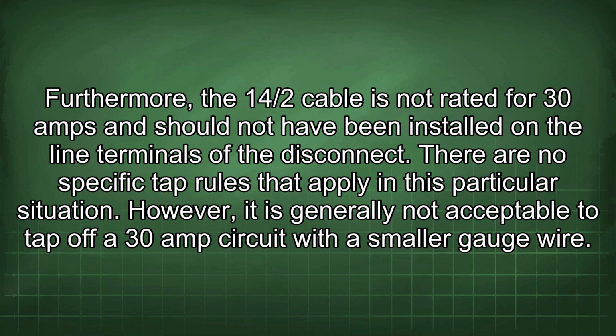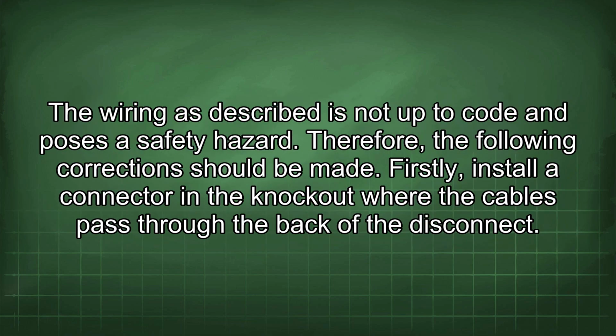of the disconnect. There are no specific tap rules that apply in this particular situation. However, it is generally not acceptable to tap off a 30 amp circuit with a smaller gauge wire. The wiring as described is not up to code and poses a safety hazard. Therefore, the following corrections should be made.